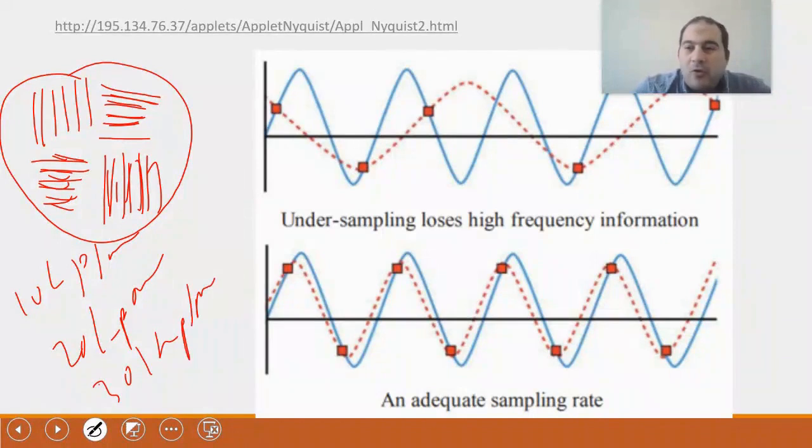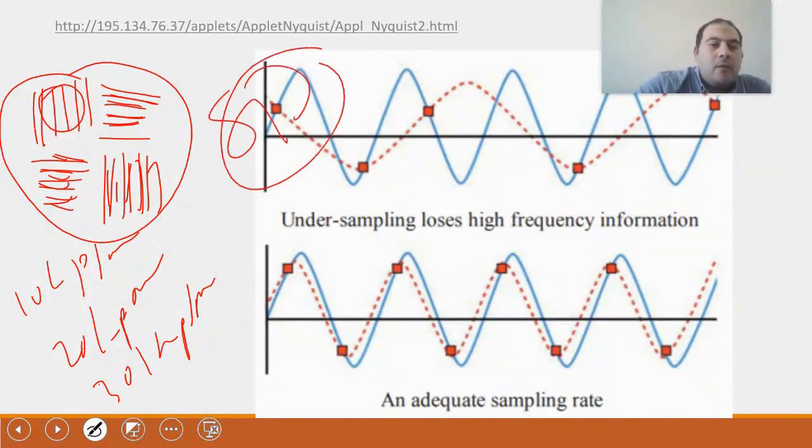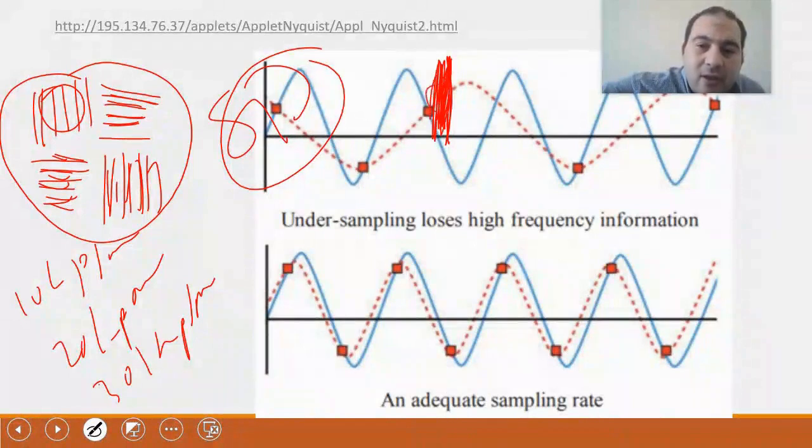Okay, each group takes a region of interest, ROI, and calculates the standard deviation. The standard deviation expresses the extent of variation present, meaning the imaging system itself can see a difference between the line pairs and the sample. If it sees all the line pairs as one entity, without differentiation, it will perceive them all as the same. So, when I take the ROI, I find that my standard deviation is very low.